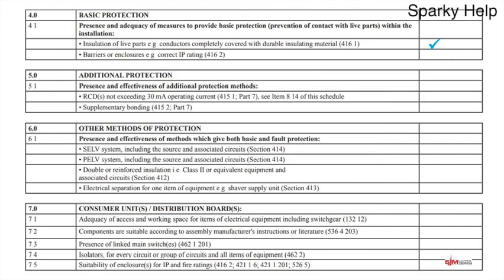If accessible, the horizontal top surface of a barrier or enclosure shall provide a degree of protection of IPXXD or IP4X. What is that? That is a 1 mm diameter piece of wire, effectively. That's what they test it for. So that's what we're effectively looking at when we do that. So we shouldn't be able to get it in. The front, sides, back, if accessible, and the bottom of an enclosure mustn't let your finger in, which is IP2X, and the top is IP4X. Why higher on the top? Well, gravity will make things settle on the top. So if you were in a dusty environment, or over time, if your holes were too big, eventually it would fill up.